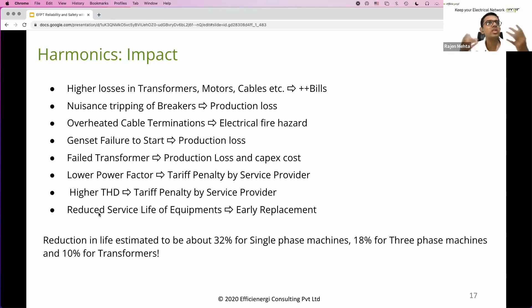That's when Ohm's law comes into play, and your high impedance and high harmonic current cause your voltage harmonic to increase. That's when you can possibly expect equipment to start malfunctioning, but not because of current harmonics. More often than not, we find that downstream, not at the PCC, current harmonics are higher, say near a VFD-driven chiller, but it doesn't cause problems to your CNC equipment, because the voltage harmonics is well within limits and you have an almost sinusoidal waveform.